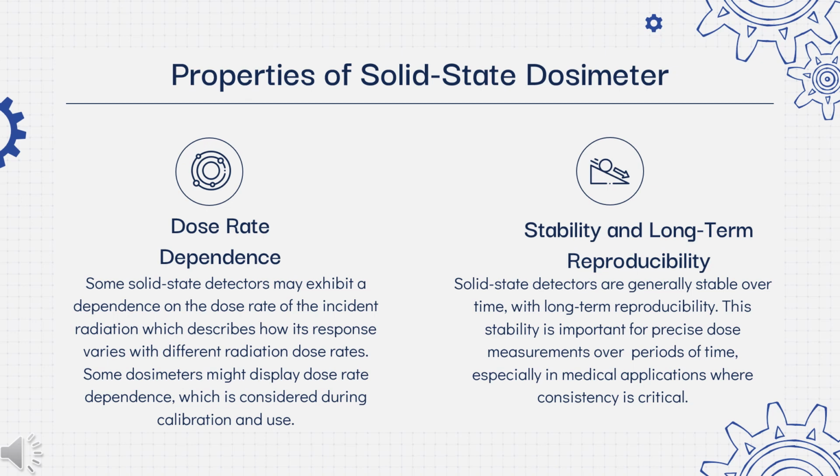Stability and long-term reproducibility. Solid-state detectors are generally stable over time with long-term reproducibility. This stability is important for precise dose measurement over periods of time, especially in medical applications where consistency is critical.